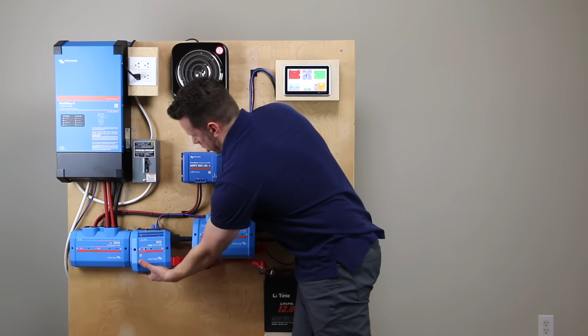So the power in does not have any fuse locations, and it's going to be where your batteries connect, and then they run through either the shunt or the BMS to get to the distributor, and that's going to measure everything between the batteries and the rest of your system. So it's a very clean setup.